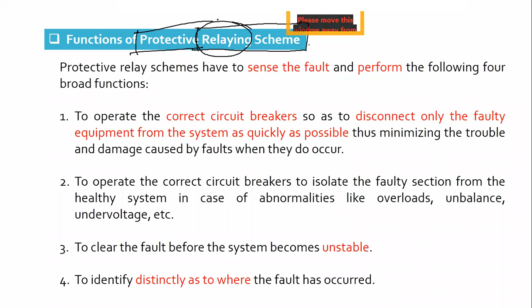What do we mean by protective scheme? It is not only the relay. The relay has to sense the fault, and it has to perform a few functions. What is the first function it has to perform? It has to operate the correct circuit breaker and disconnect the faulty part from the rest of the healthy system as quickly as possible, so that it will minimize any possible damage due to fault.